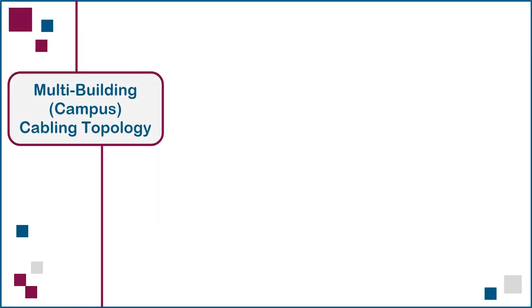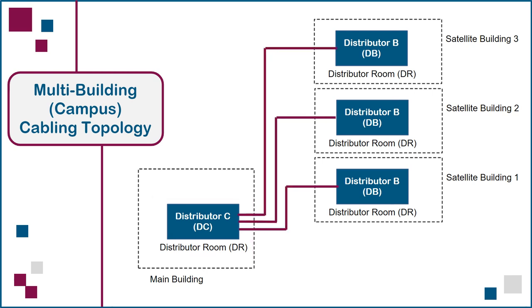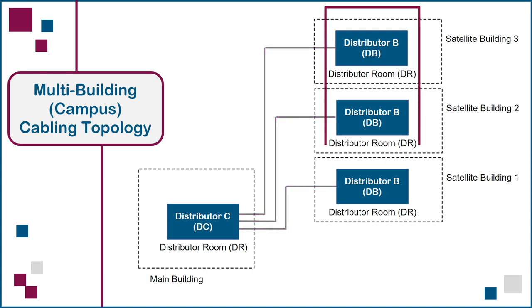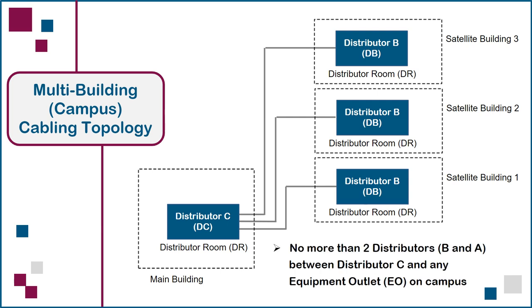Next, we'll apply the generic cabling model to a multi-building or campus environment. In this top-down view of a four-building campus, the distributor room in the main building on the left contains Distributor C, or the campus distributor. Outdoor backbone cabling connects this campus distributor to individual building distributors, or Distributor B's, in each of the three satellite buildings. Note that because this is a top-down view, the distributor rooms containing Distributor A's on each floor of every building cannot be shown. With this design, there are no more than two distributors, B and A, between Distributor C in the main building and any equipment outlet on any floor, anywhere on campus.